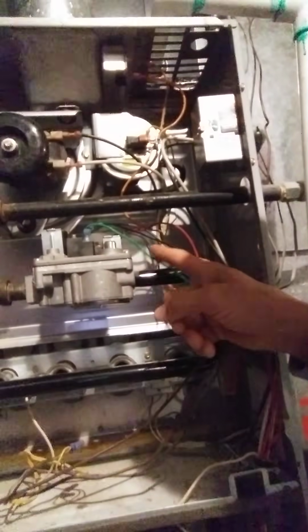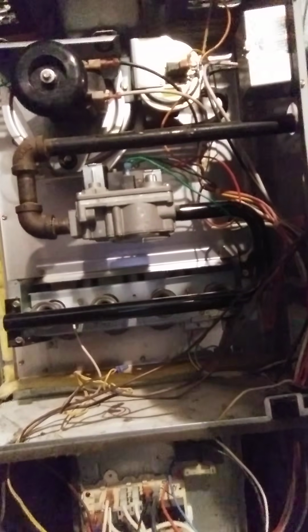It glows up pretty hot to ignite the gases whenever there's gases coming out. And then to detect that, there's a flame sensor up here that goes into the flutes, and that detects that there's actual ignition, actual flame. If any of them are not functioning properly, your system will not run. And there's different diagnostics for those types of things. We won't get into that today. But basically what we're doing again is we're trying to follow the wiring throughout the system and to the different sensors. And then there's a method of bypassing the sensors one by one to try to narrow down exactly where the breakage is at.